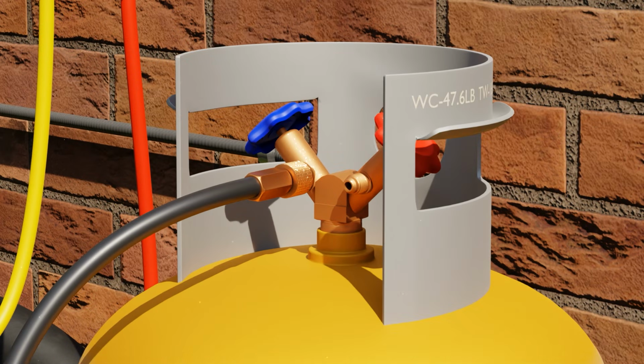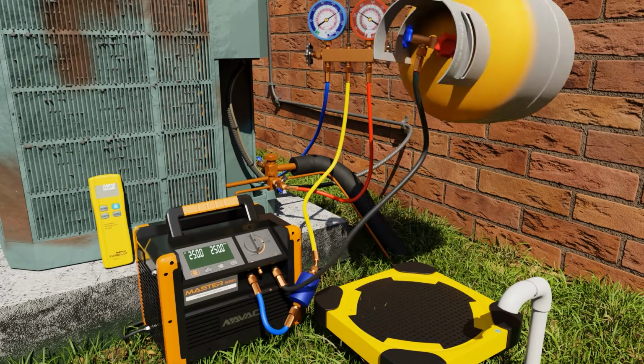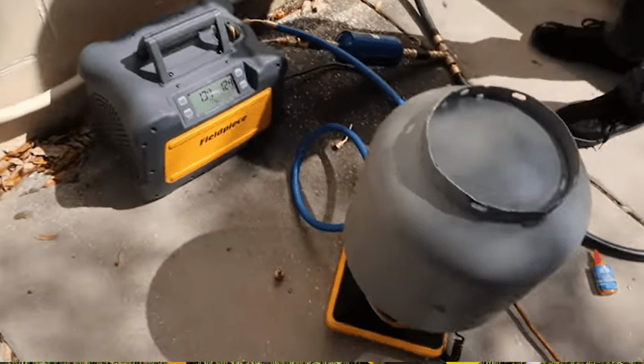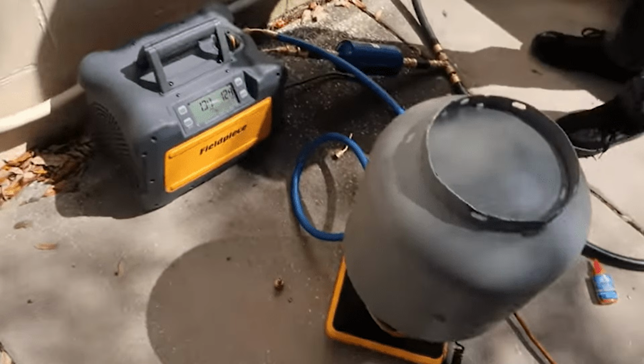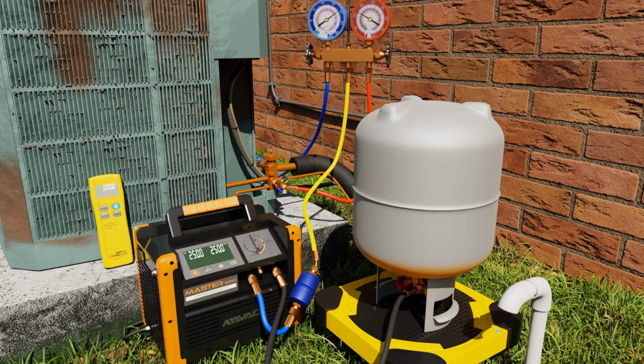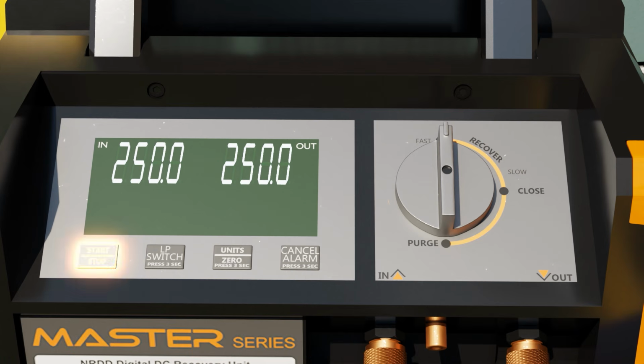Now you can recover. Here we show inverting the tank first. Recovering into the vapor side of the tank with the tank inverted has been shown to be the fastest way to recover because you don't have a dip tube on the vapor side of the tank. And inverting it just ensures that you're filling from the bottom up, which helps dissipate heat a bit more easily. It's not a huge difference, though, if you invert the tank or keep it right side up, so do whatever seems best to you. You can start your recovery machine now.